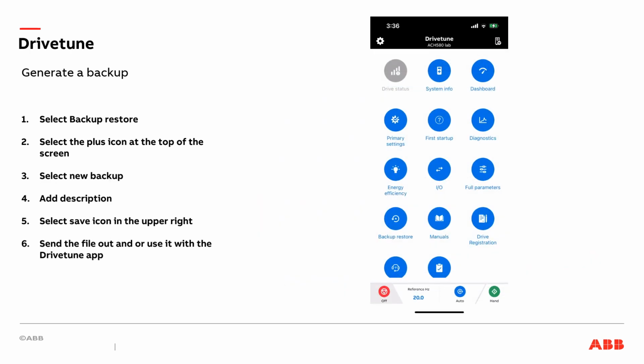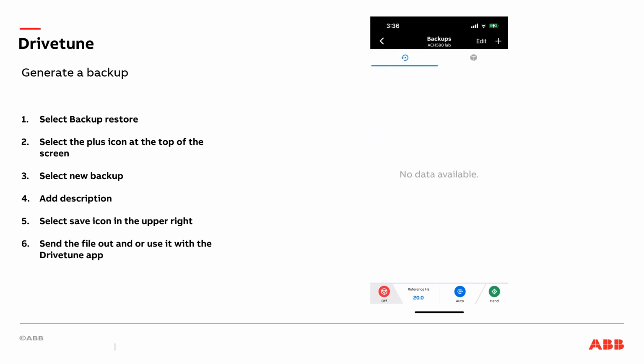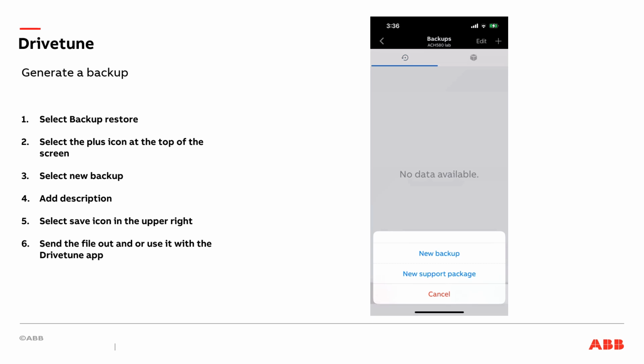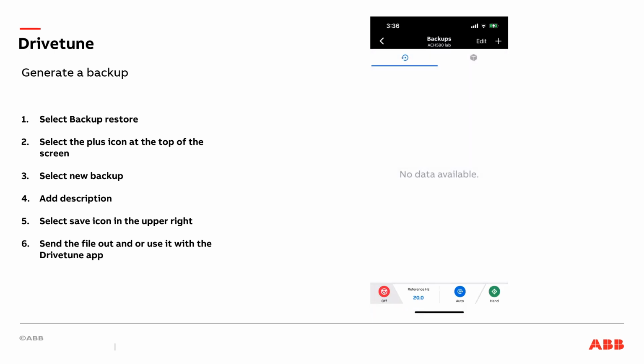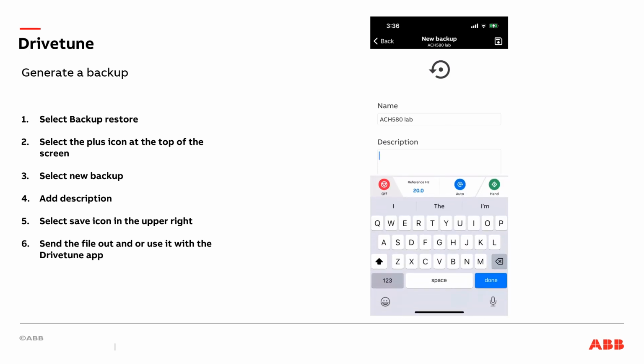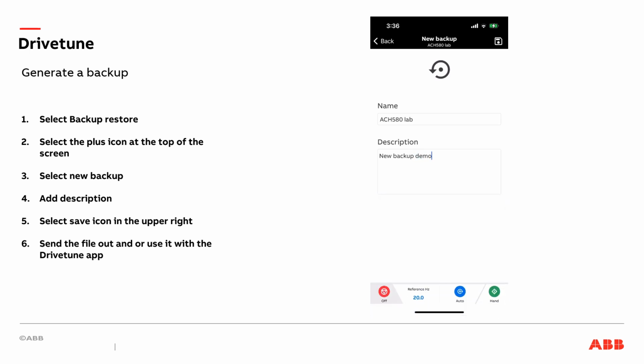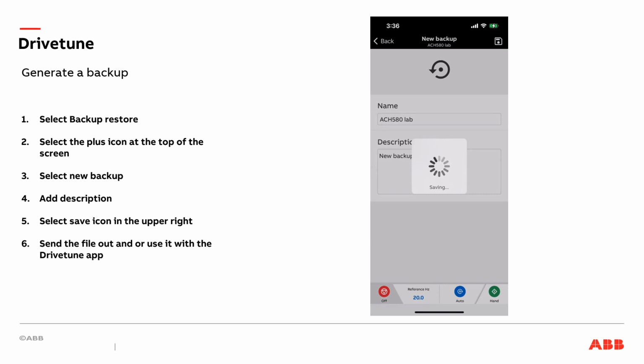I will now demonstrate the creation of the backup file after connecting. After selecting the Backup and Restore button, in the next screen, you will select the plus button. You will then select new backup. I like to add detail to the description of the file for reference. I then hit the save icon in the upper right-hand corner of the screen, and this will generate the file. It will take approximately 2 to 3 minutes for the backup file to be created. In that time, the backup file being created will contain all the programming data in the drive. This file is typically created when the site is commissioned and retained for records or simplification of programming for other similar drives.